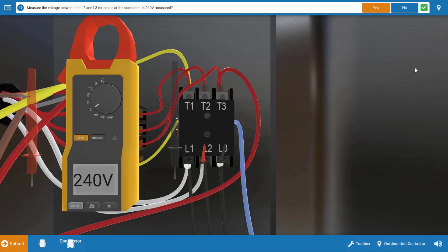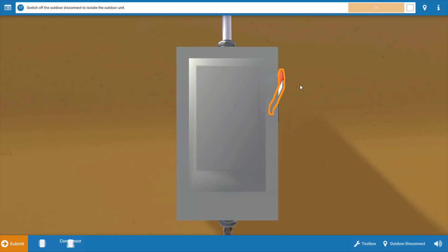Now it's a little more invasive to check the contactor, so what we're going to do here after clicking yes that we measured 240, we're going to turn the power off and we're going to do some resistance checks of the heaters and possibly the motor windings first.